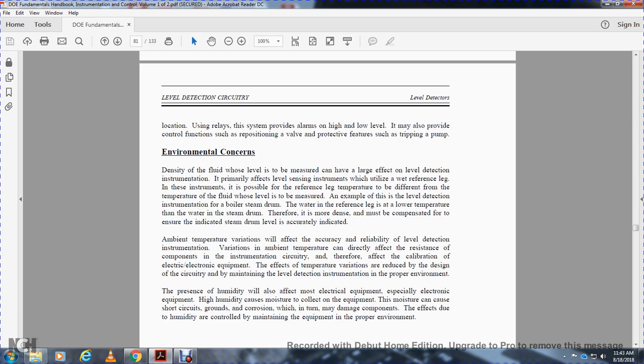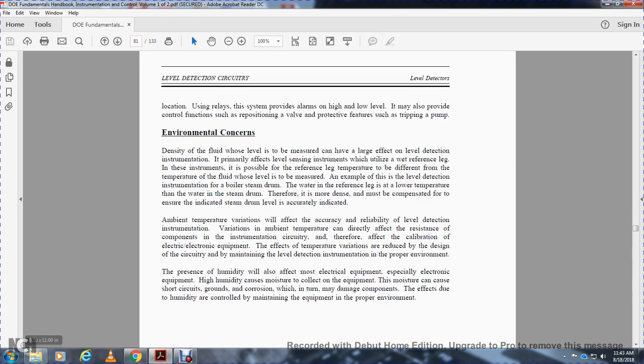Ambient temperature variation affects the accuracy and reliability of the level detection instrument. The variation in ambient temperature can directly affect the resistance of the components of the instrument circuitry and therefore affect the calibration of electric and electronic equipment. The circuitry is designed to reduce the temperature variation effects and maintain the level detection instrumentation in a proper environment. Humidity will also affect most electrical equipment, especially electronic equipment.